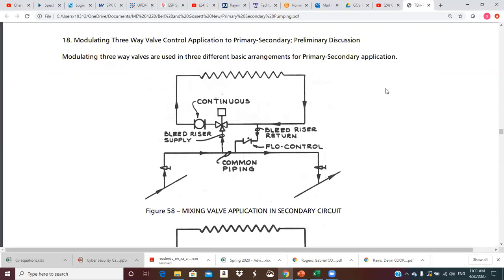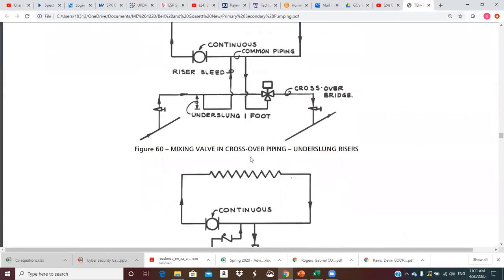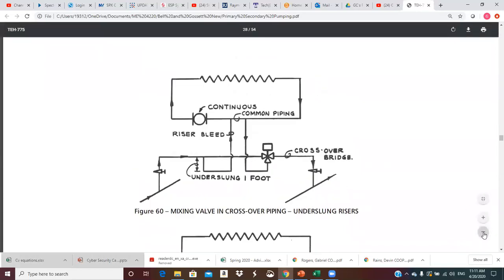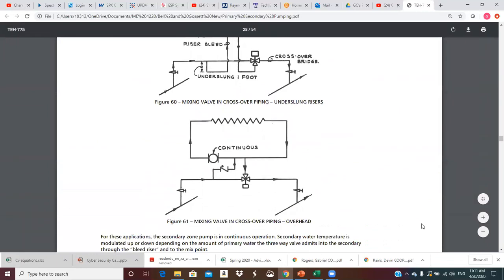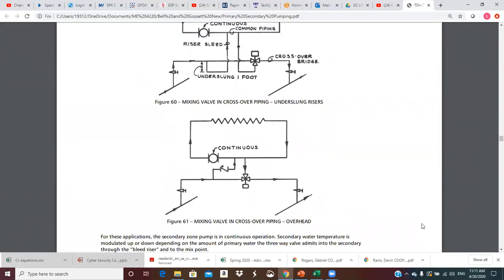Problem three: this valve is line-sized to the secondary flow rate. If the flow I'm actually trying to control is much less than the secondary flow, the valve is oversized for the flow it's trying to control, and you don't get good controllability. So those are the three reasons we don't really like figure 58 and much prefer arrangements 59 or 60.